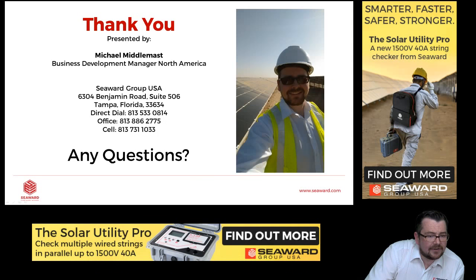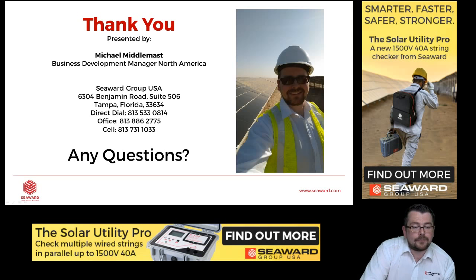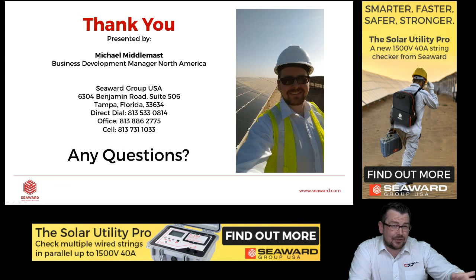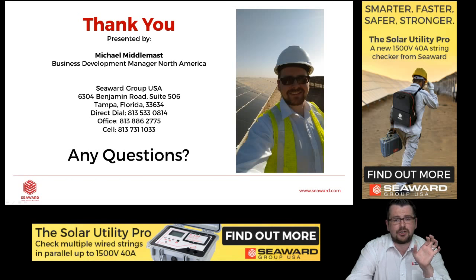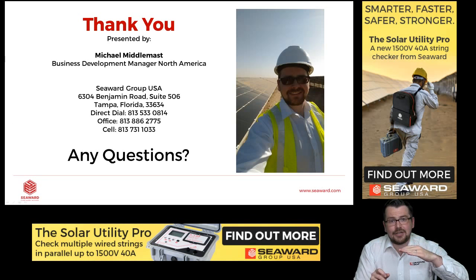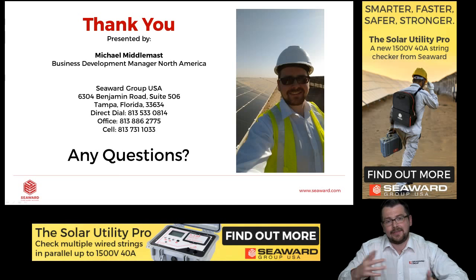Okay, question. Even if insulation resistance is less than 1 megohm, will the generation be still up and running? If yes, why? This really depends on the size of the string, I guess. But as I just mentioned, insulation resistance and short circuit current, they go hand in hand. So if your insulation resistance is low, generally your short circuit current will be low as well, and that will cause losses of generation.